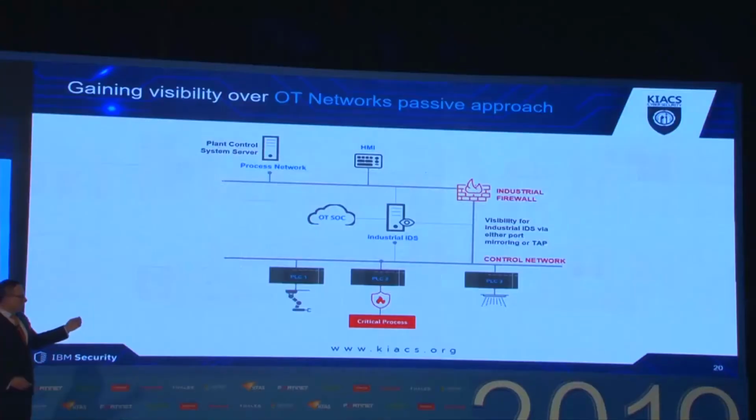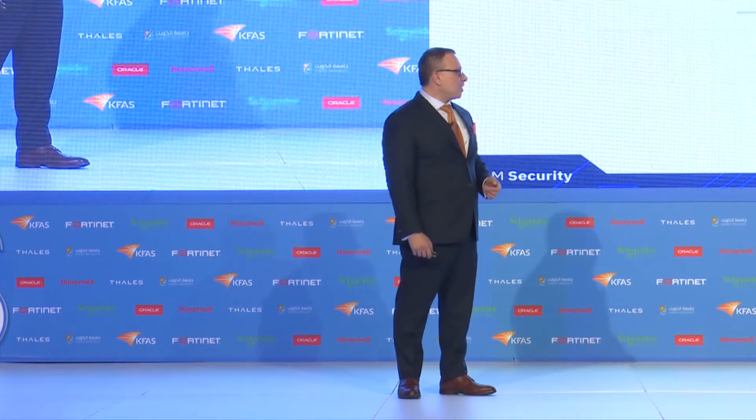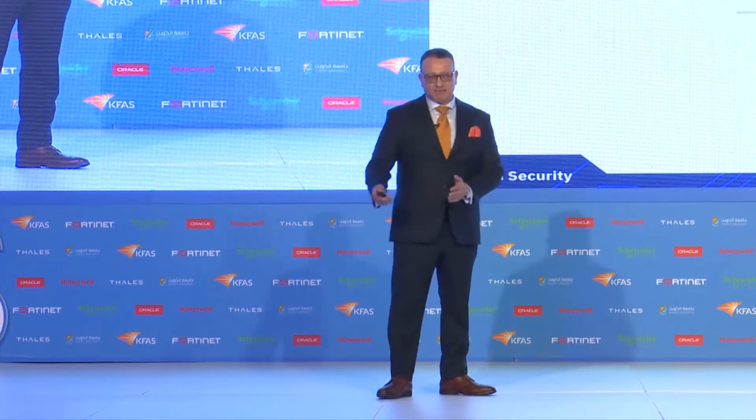For the OT side, the method that we used to gain visibility into the OT environment is an industrial IDS. There are many on the market, but what it allows us to do is to take a look at PLCs and other OT equipment and to attain telemetry data. We do this by what we call mirroring of the port, meaning in a passive mode, not in a mode where we could cause maybe unintended problems to the production.